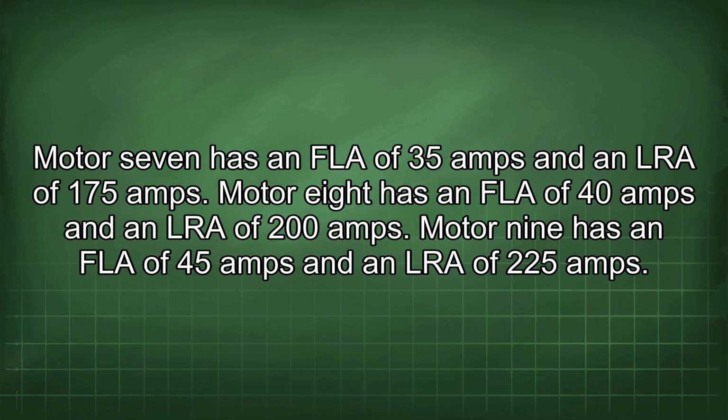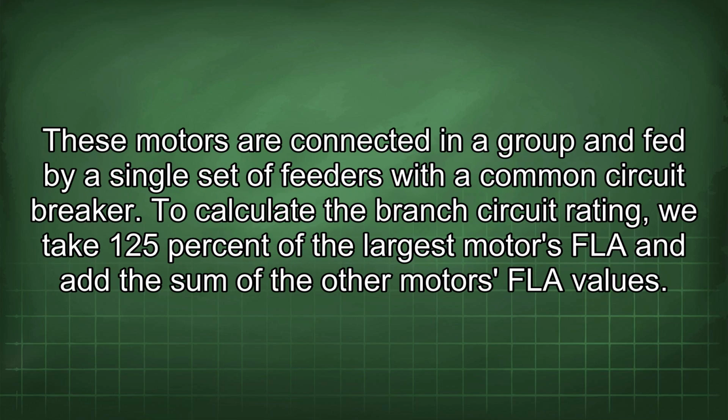Motor 8 has an FLA of 40 amps and an LRA of 200 amps. Motor 9 has an FLA of 45 amps and an LRA of 225 amps. These motors are connected in a group and fed by a single set of feeders with a common circuit breaker.